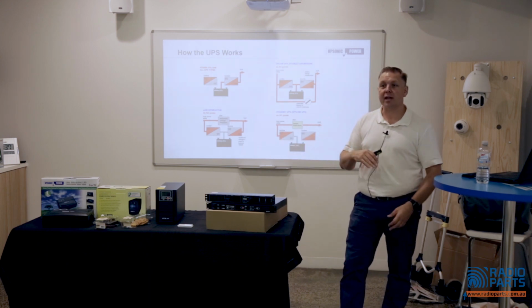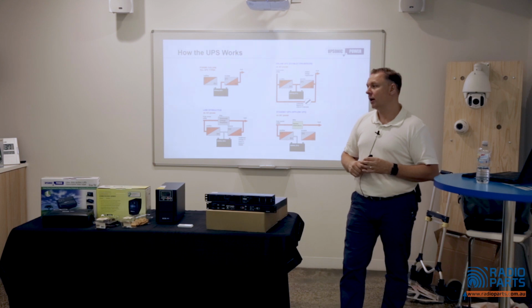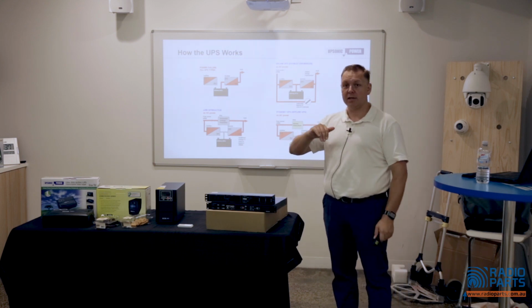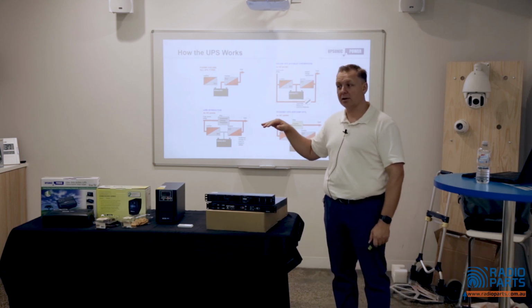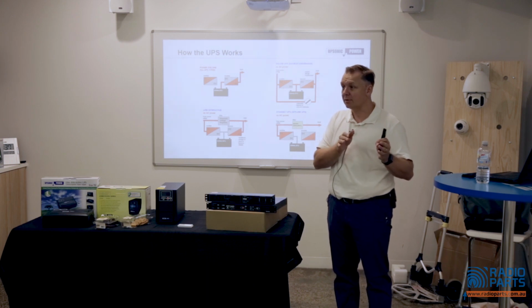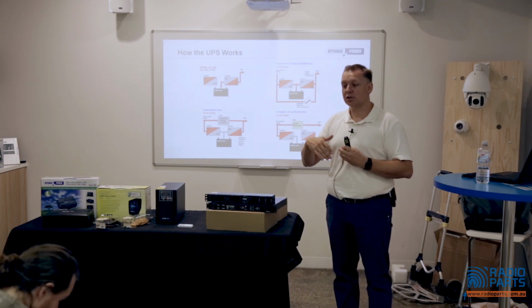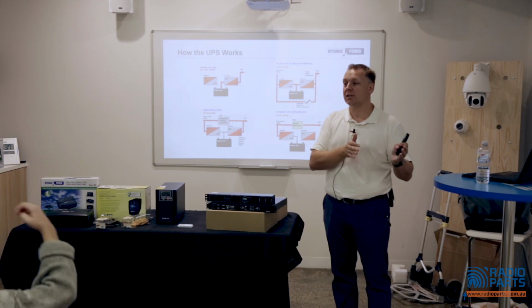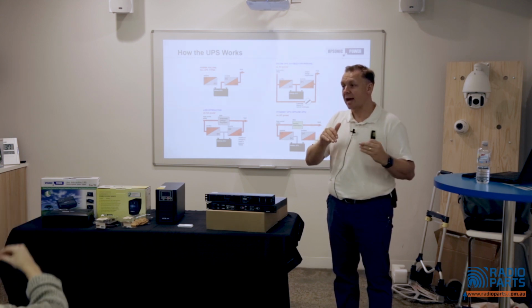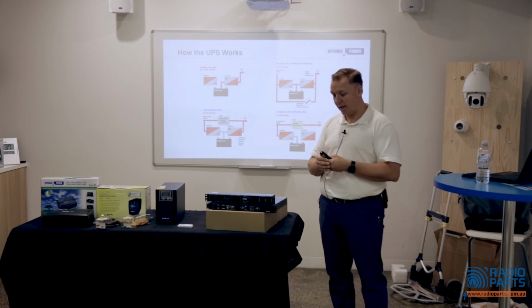The line interactive unit can do what we call buck and boost. So if you're getting spikes, it can smooth those out and still actually be running on mains. It's smoothing out those spikes. And also if you get a slight brownout, it can continue to run mostly from the mains and use the battery just to boost that voltage.